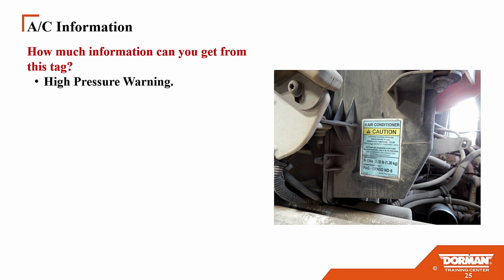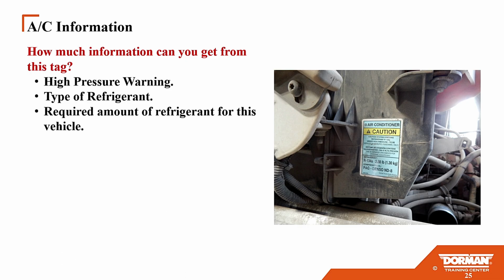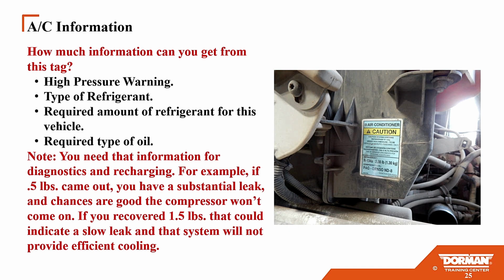High pressure warning, of course, on this one. Type of refrigerant, absolutely. Required amount, that's crucial, okay. Required type of oil, absolutely, okay. You need that information for diagnostics. Everybody says PAG oil, but keep in mind too, there's different weights of PAG oil, so you can't just do the universal thing anymore. So especially if you're changing compressors and stuff, you've got to be careful.